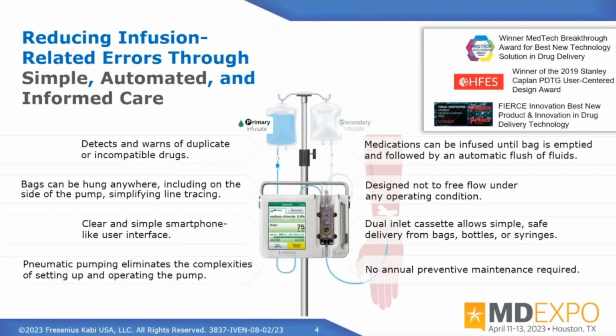When we remove the cassette, we actually have to have the device stopped. So the nurse will have to stop the device in order to remove the cassette. And that's so that this flow dial can close, so that we're guaranteed a flow dial closure and no free flow. So there are a lot of issues in the market today with free flow with different devices. Plastic pieces are breaking and free flow can occur. This is intended to address that fully so that it's certain that it won't free flow.